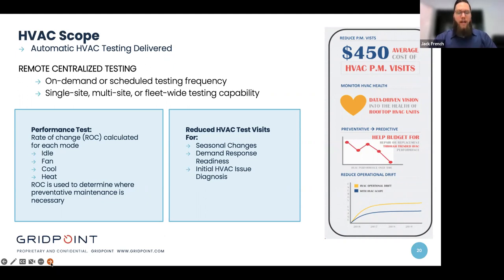So running this before we end up in the cooling season keeps us from being put on the back foot and ending up in a reactive situation. This can also help for demand response readiness. Do you want to make sure that you are able to shave the peak that you're nominating? Then you want to make sure that your equipment is in good working order mechanically, and this is a good way to do that. This gives you ammunition to say, hey, where do I have opportunities to focus? And then of course, initial HVAC issue diagnosis.